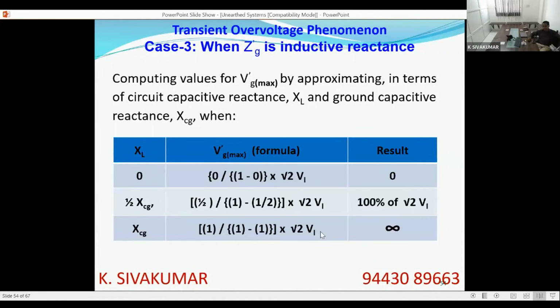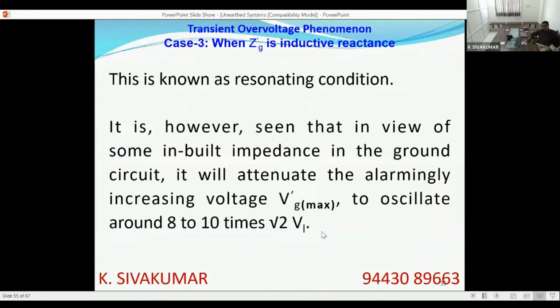Whenever the external impedance equates the leakage capacitance of the system, there is a tendency of the voltage appearing across the external load going towards infinity. That is, very high voltage will be thrust upon the equipment and system during a single phase ground fault in an unearthed system. So this is known as the resonance condition. However, in view of the inbuilt resistance in the ground circuit, it will be attenuated, not practically infinity. There have been calculations.